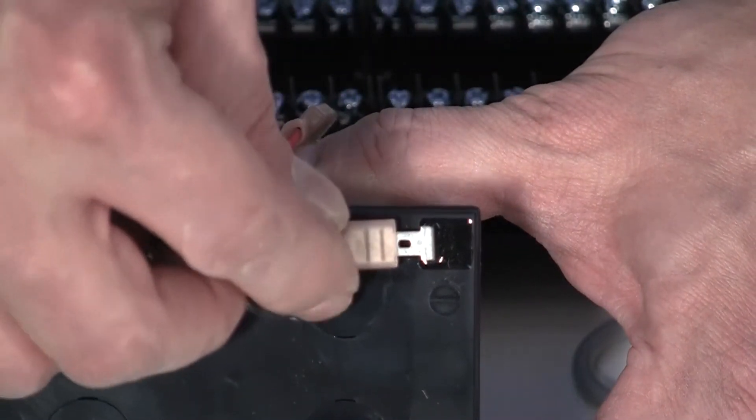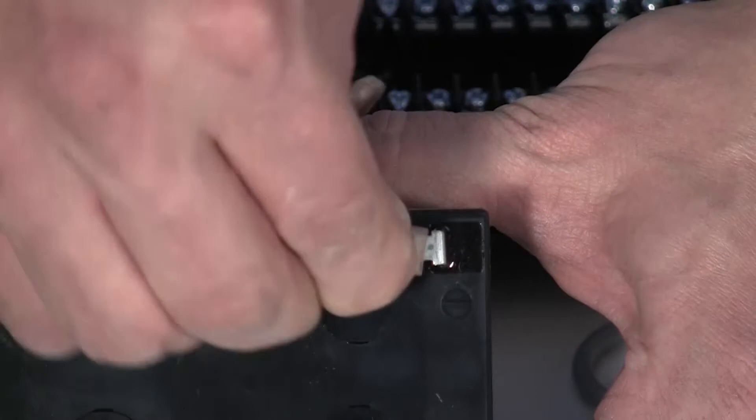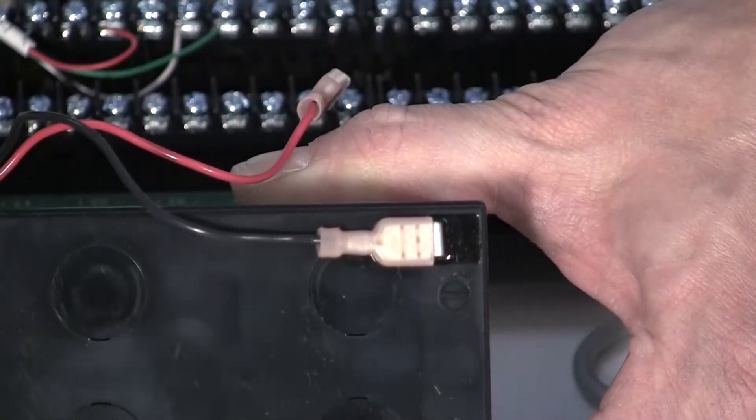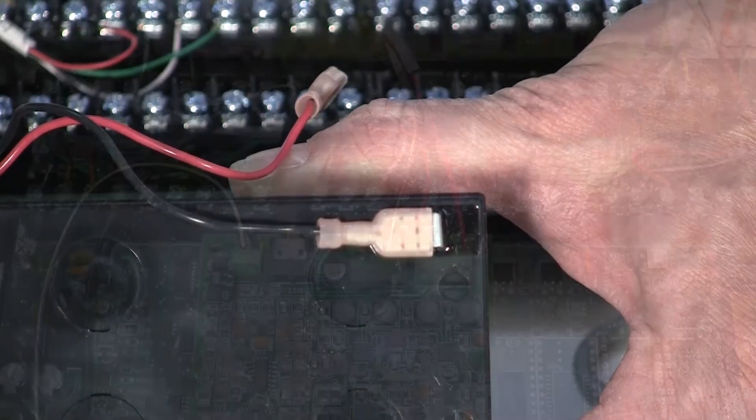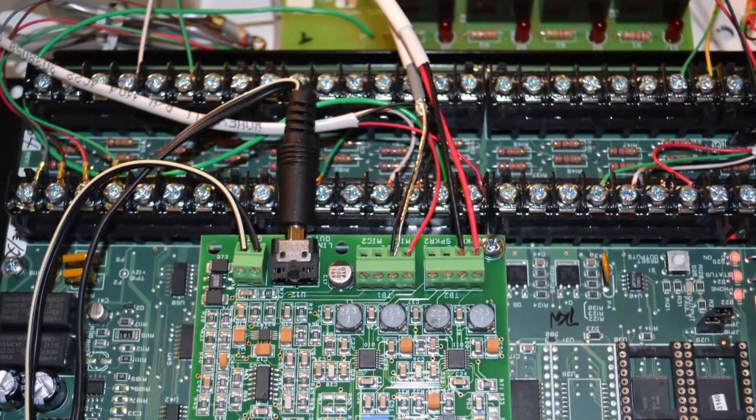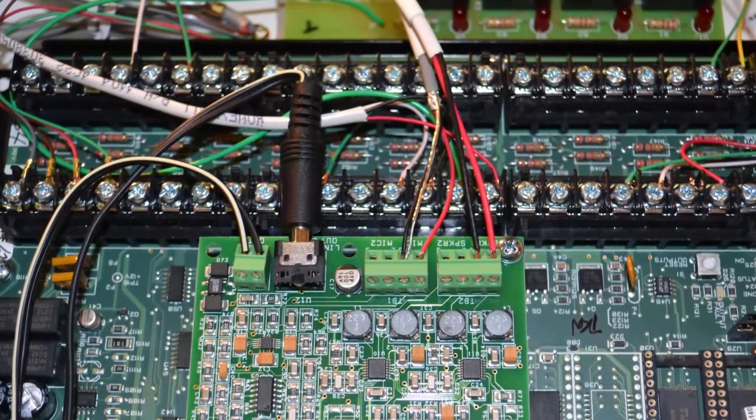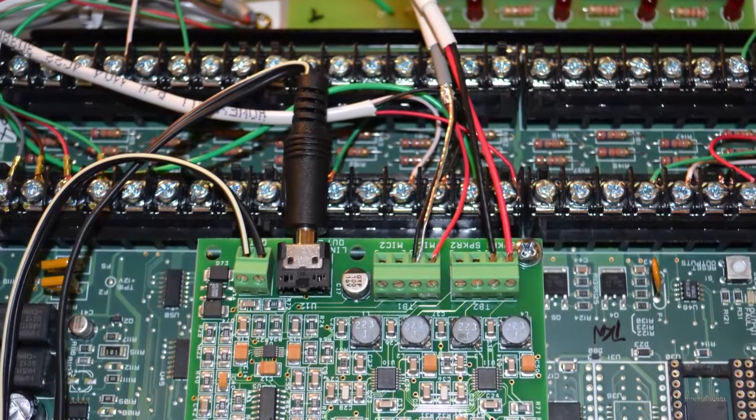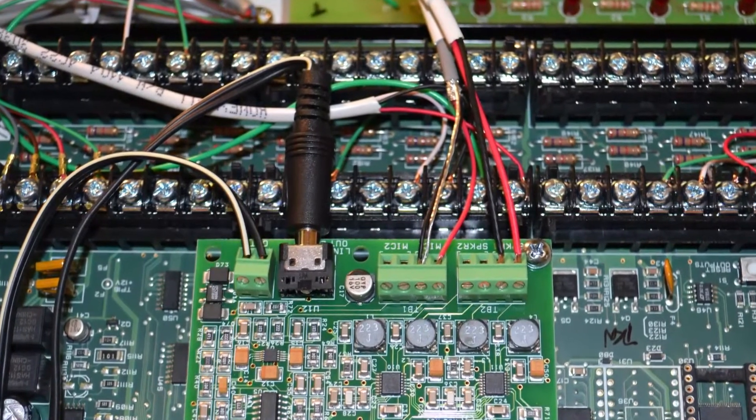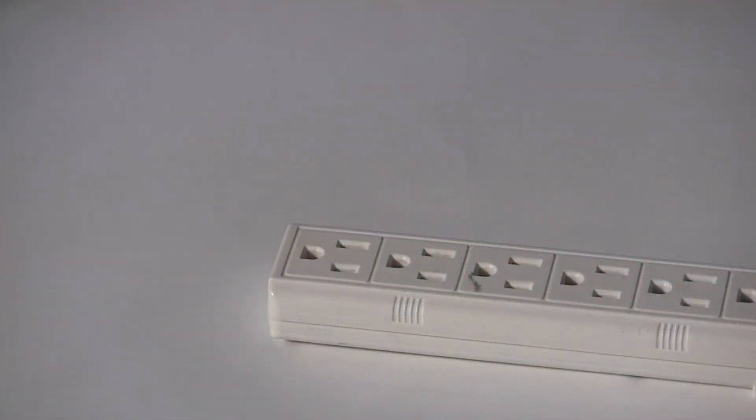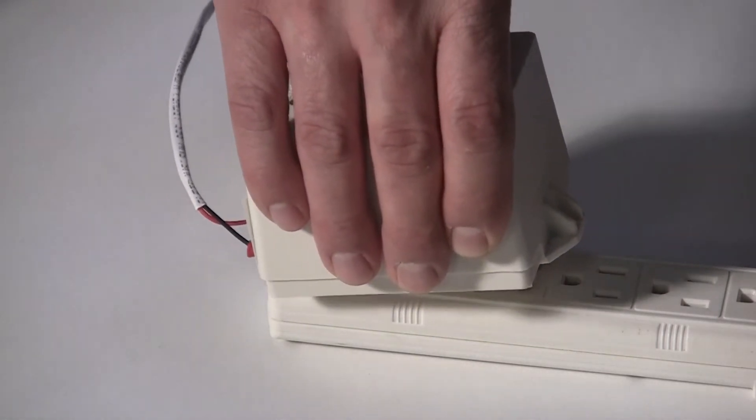The unit will not power up on the battery alone. The battery leads must be separated from all other power limited class II wiring in the enclosure by at least a quarter inch. We have completed the physical installation of the controller itself at this time. Check all connections.